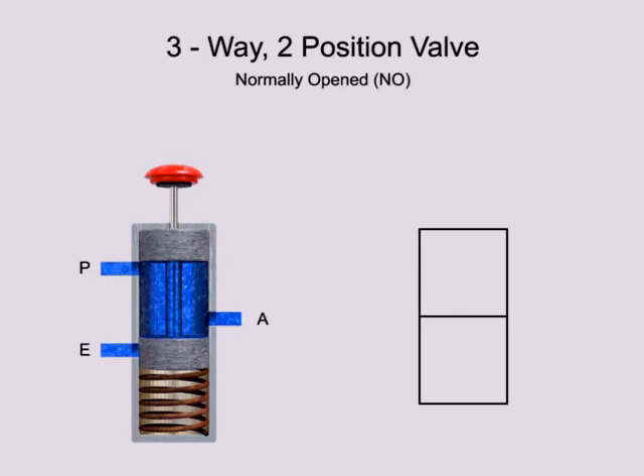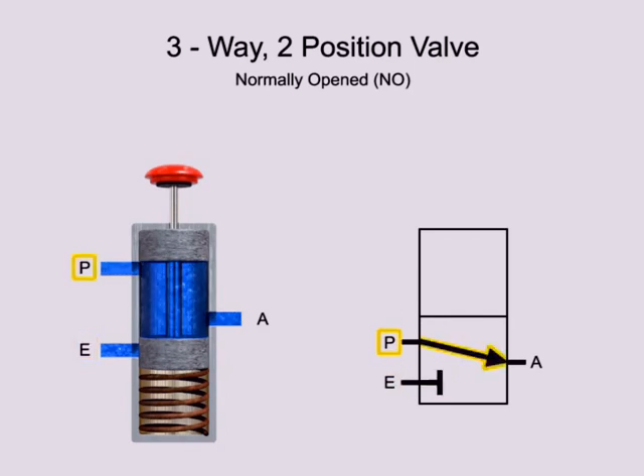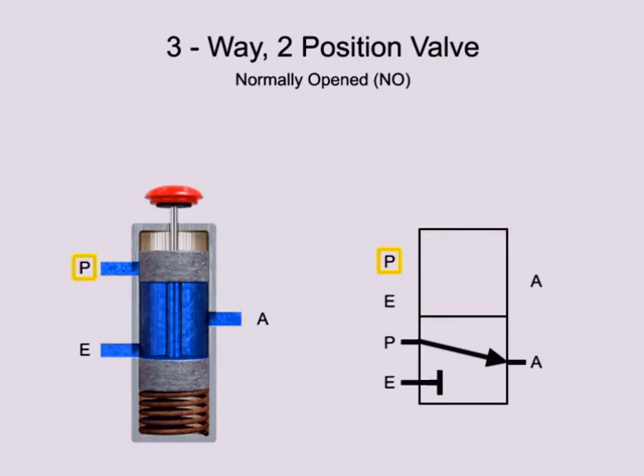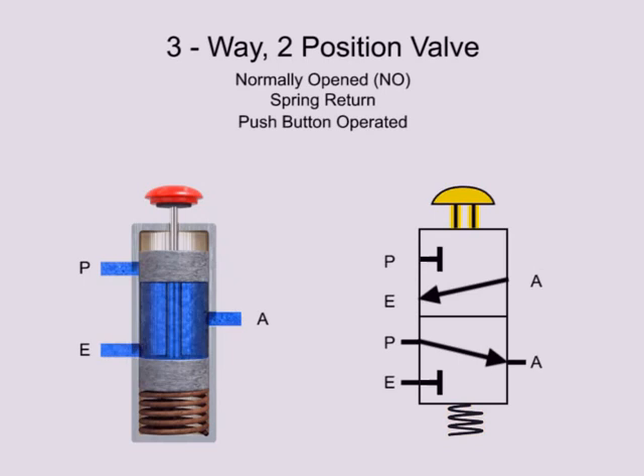Here is another three-way, two-position valve. This valve also has an inlet port P, exhaust port E, and output port A, but they are in a different configuration. In its normal position, exhaust port E is blocked and fluid flows from pressure port P to outlet port A. In the second position, pressure port P is blocked and fluid is allowed to flow from outlet port A to exhaust port E. The valve is also spring return and push button operated.